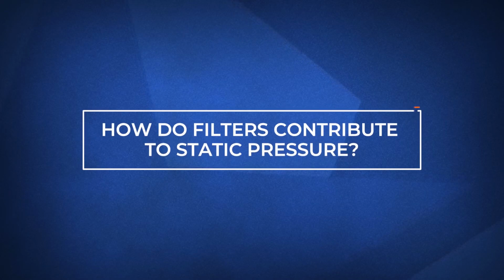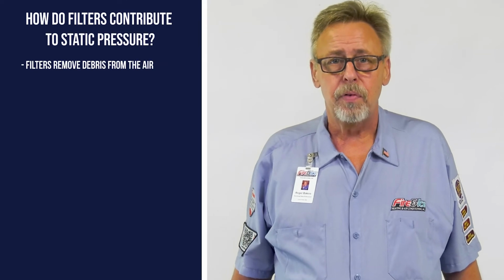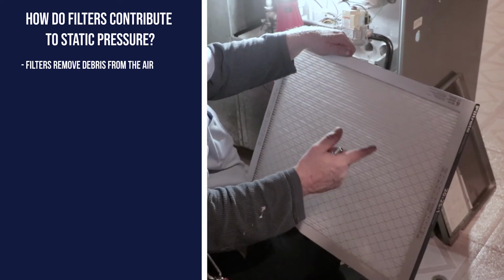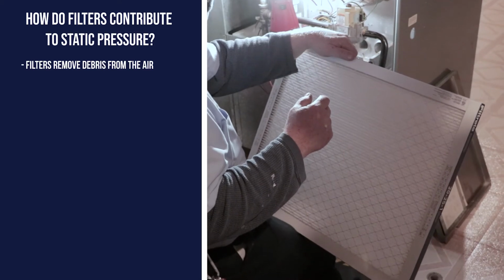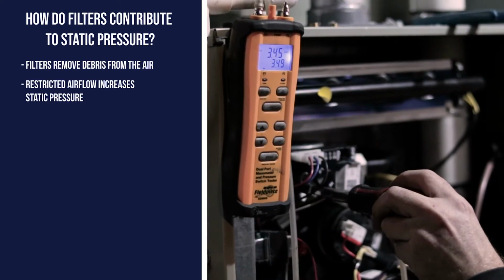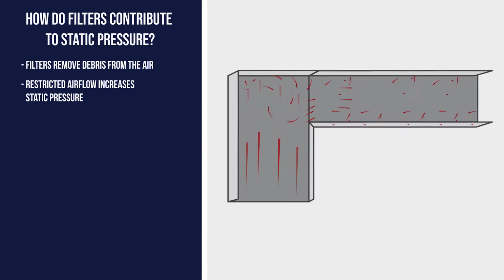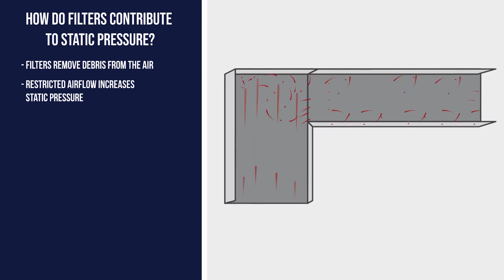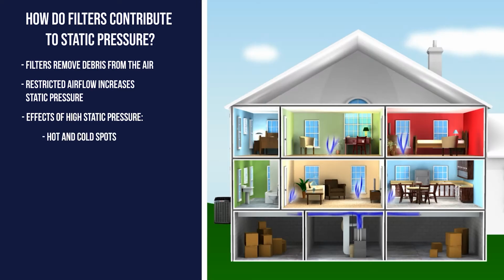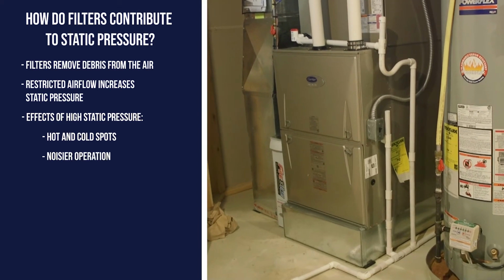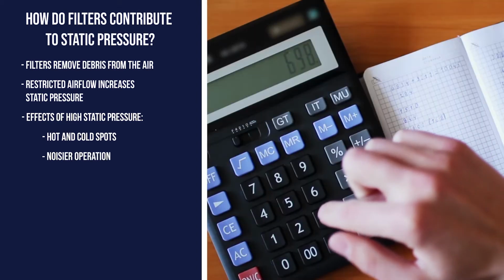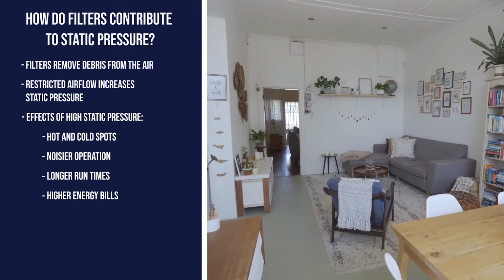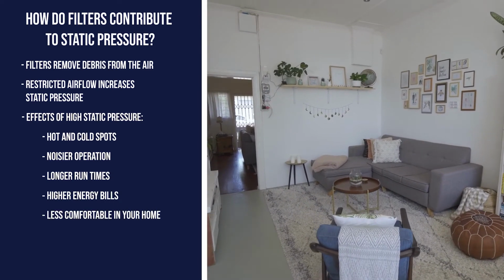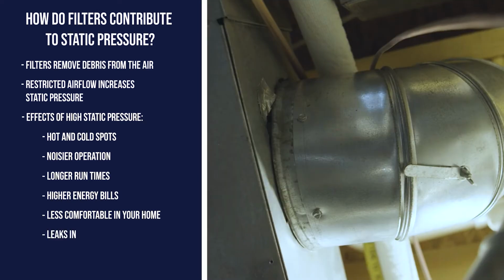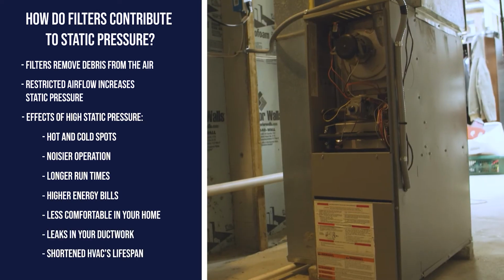How do filters contribute to static pressure? A furnace filter is designed to remove debris from the air. As time goes on, the debris builds up and restricts the amount of air that is able to flow through the filter. Restricted airflow can cause an increase in static pressure. This airflow backup makes your system work harder and in the short term cause pockets of hot and cold spots in your home from a lack of airflow coming from the vents. Noisier operation as your system works harder. Longer run times resulting in higher energy bills, and overall less comfort in your home. Long-term effects of high static pressure can result in leaks in your ductwork and a significant reduction in your system's lifespan.